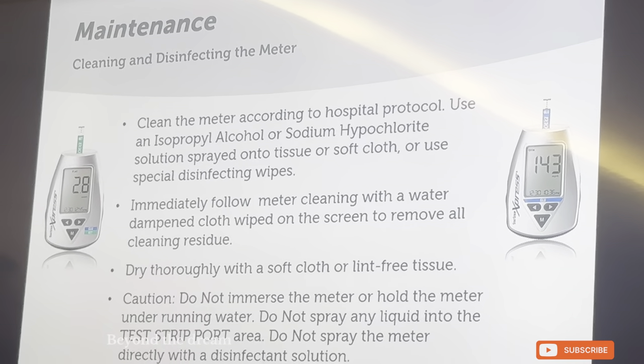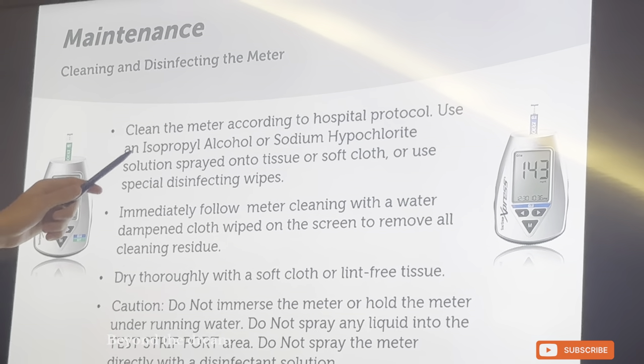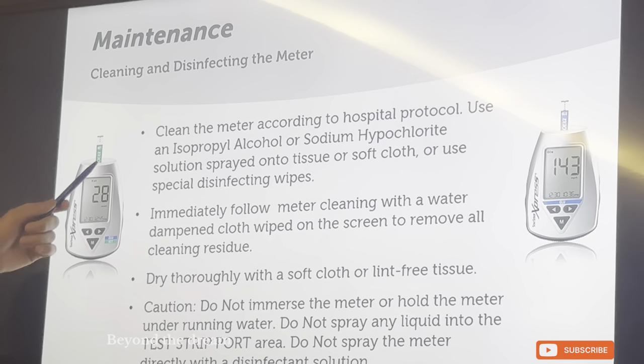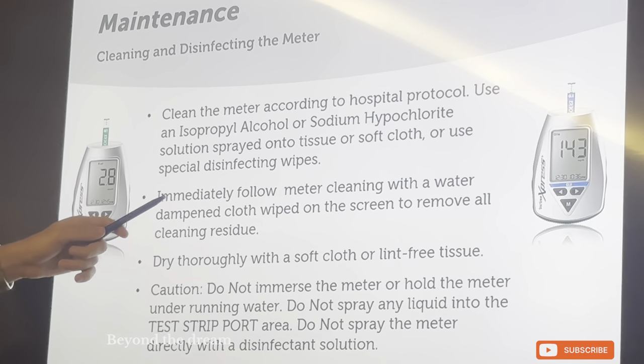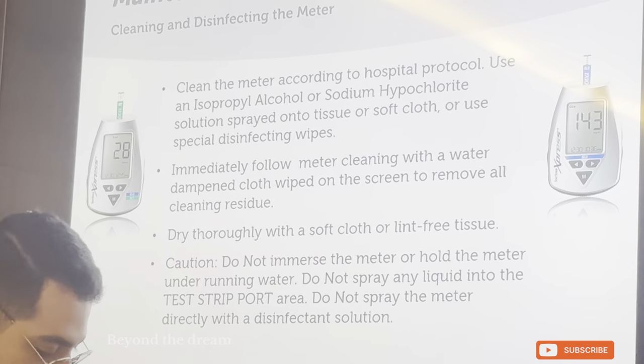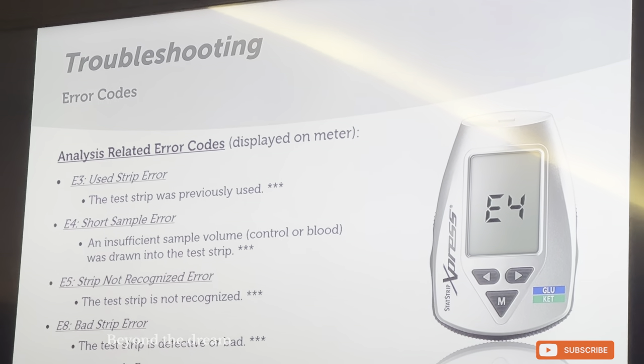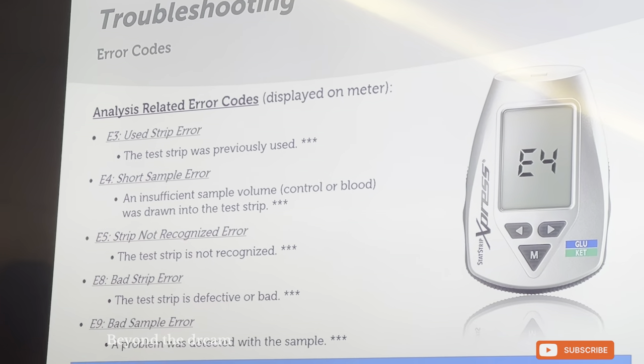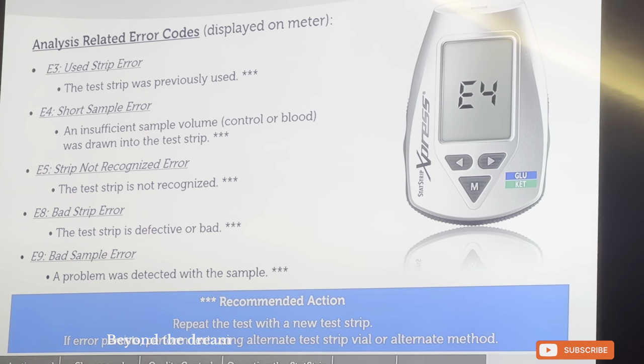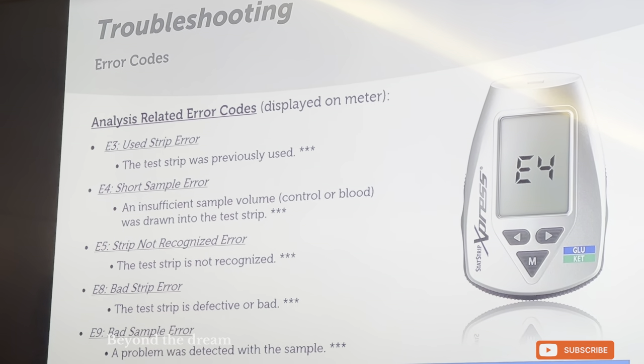For cleaning and maintenance: use three tissues or soft cloths. The first contains isopropyl alcohol or sodium hypochlorite — or whatever the hospital policy states for cleaning detergents. Clean the meter according to hospital protocol using isopropyl alcohol or sodium hypochlorite solution sprayed on a tissue or soft cloth, or use special disinfecting wipes such as alcohol wipes. There are also different error codes for the A-plus academics among you who want to understand the StatStrip Xpress meter very well.